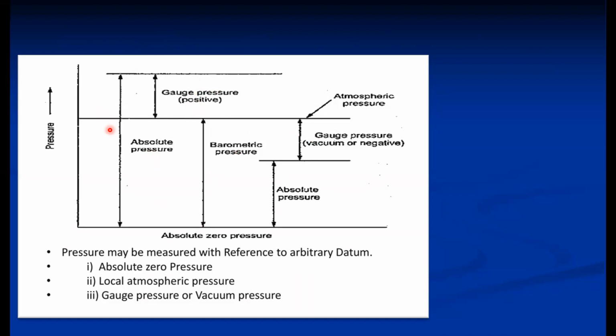If the pressure is considered as gauge, everywhere we have to consider the gauge pressure. Otherwise, if one pressure value is taken in gauge and one pressure value is given in absolute pressure, then there is an error in calculations or the answers will be wrong. So we have to be careful while considering the pressures.